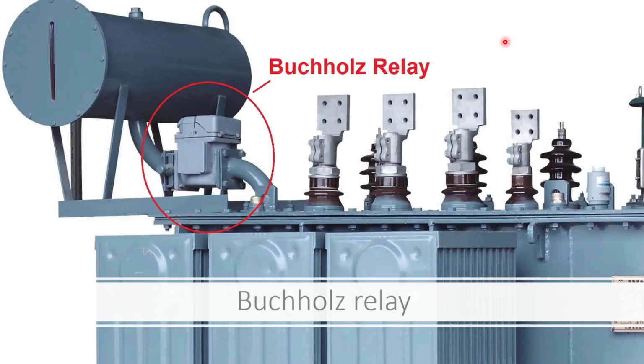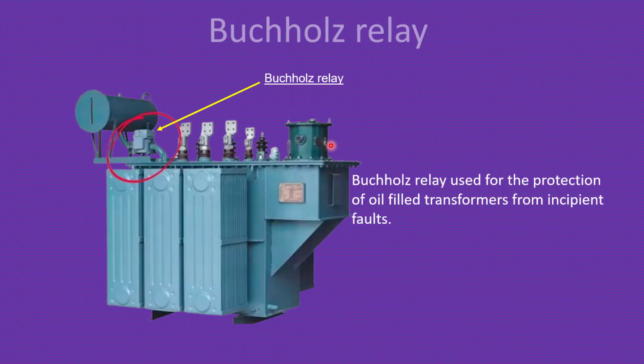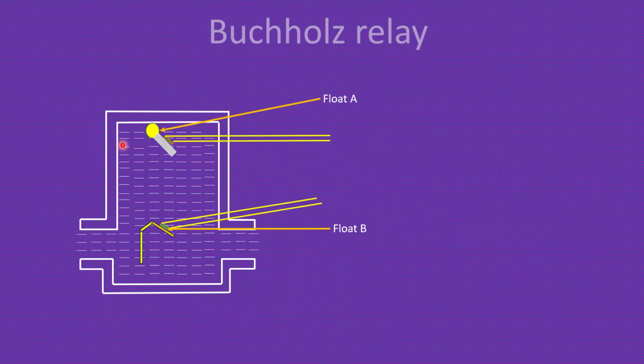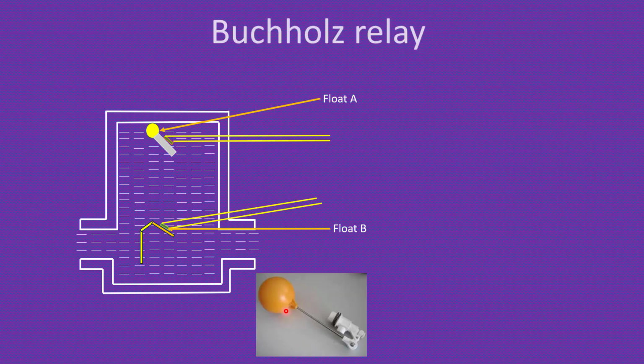The other one is the Buchholz relay. You may have seen this apparatus above the transformer. If you look closely at an oil-cooled transformer of about 250 kVA, you can see this apparatus. This is called a Buchholz relay. The function of the Buchholz relay is to protect oil-filled transformers from incipient faults. The Buchholz relay protects the transformer from faults. How does it work? Let's look into it. The Buchholz relay has two floats. For ease of imagination, you can imagine this as a float in a flush tank. It will be similar to this, right? Imagine these floats like a float in our flush tank.